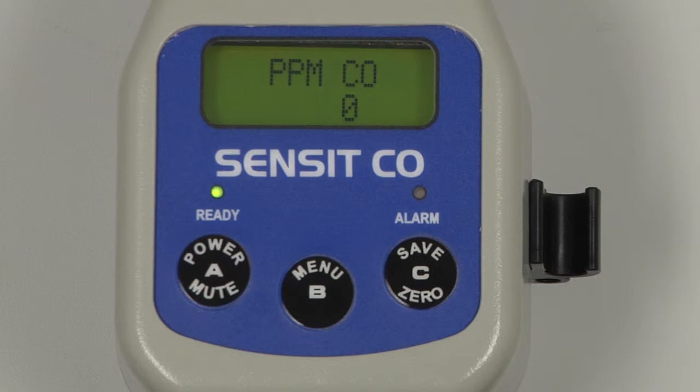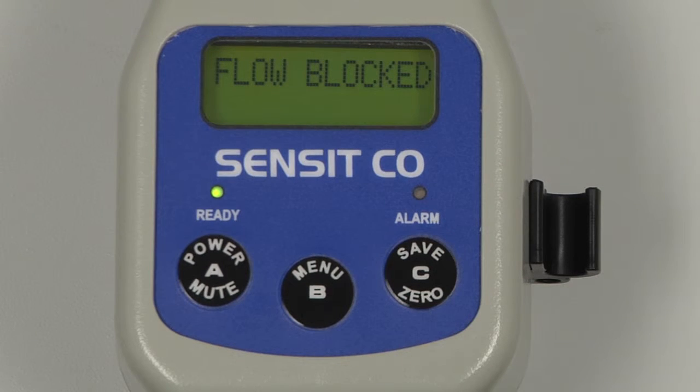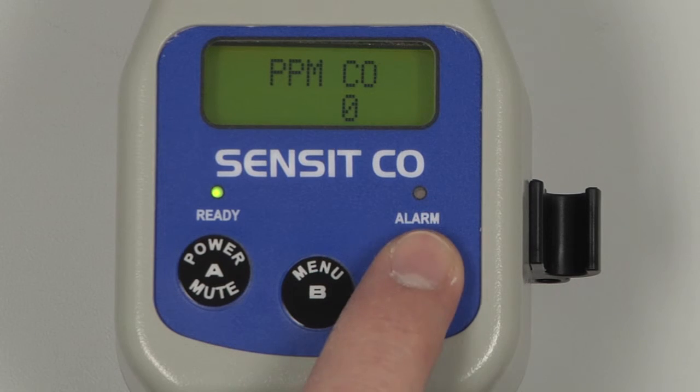To perform a flow check, block the end of the inlet with a finger until a flow blocked message appears. Allow the instrument to warm up for an additional 5-10 minutes before calibration. Prior to calibration, auto-zero the instrument by pressing and holding the C button.